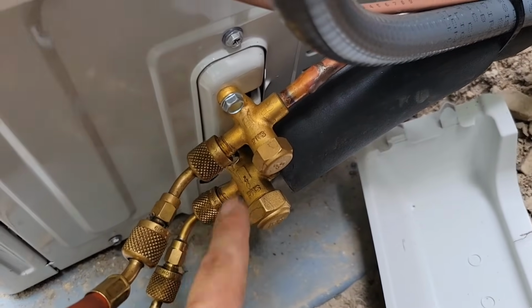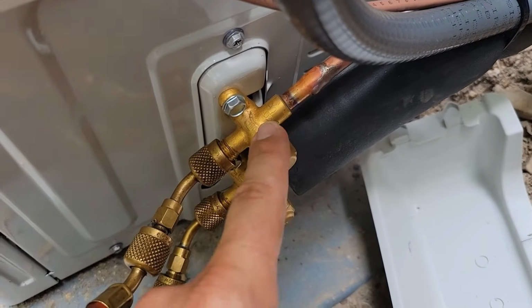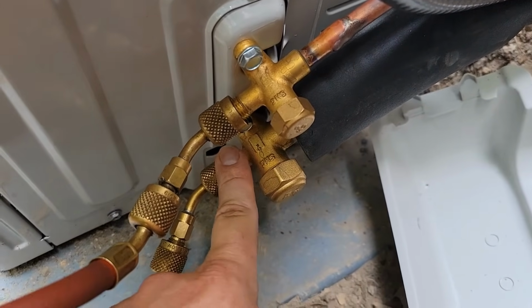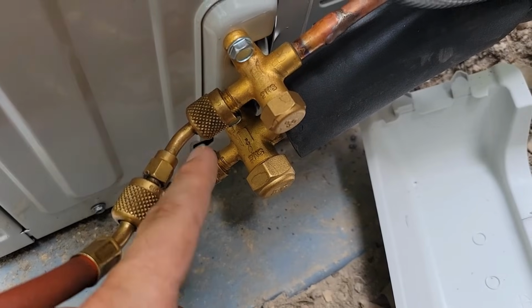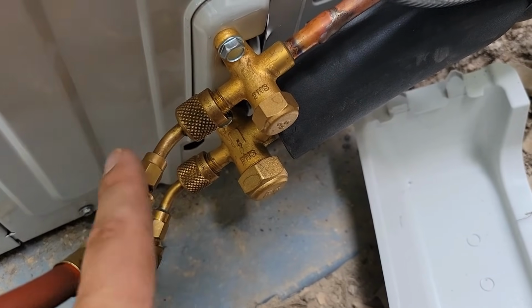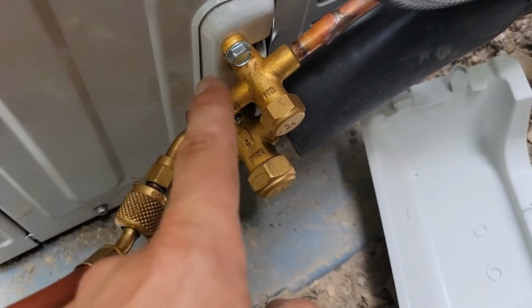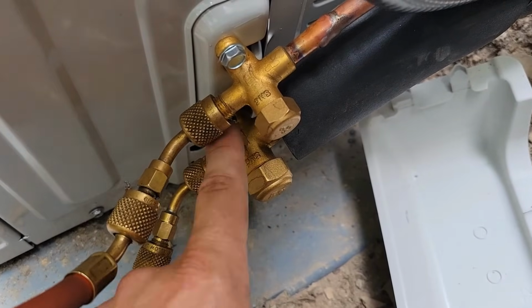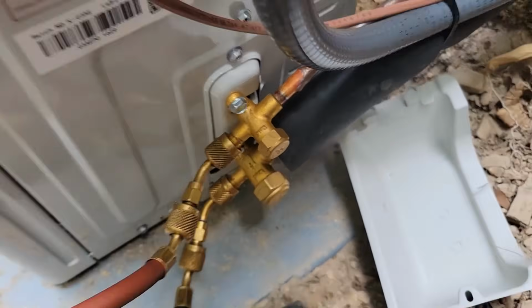Love the fact that you've got 2 ports out here that you can connect to, the liquid line service valve and the vapor line service valve. You've got to have the adapter though, from your 1/4 inch to 5/16. So make sure you have the adapter. Link in the description for that adapter.